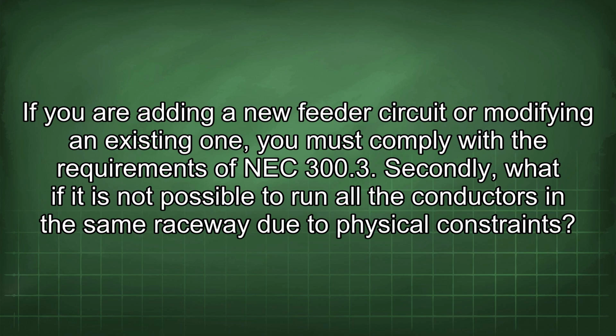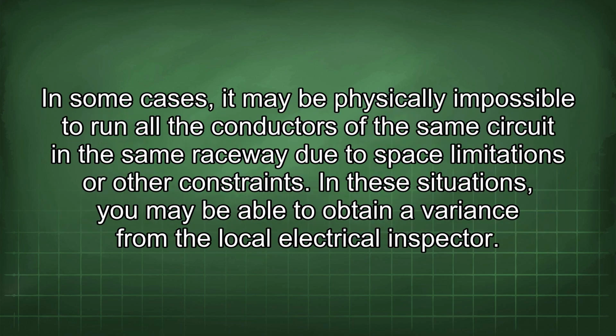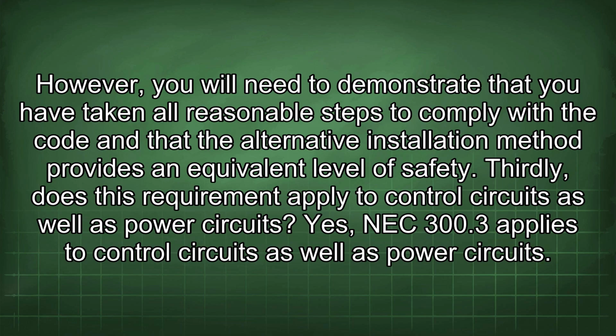Secondly, what if it is not possible to run all the conductors in the same raceway due to physical constraints? In some cases, it may be physically impossible to run all the conductors of the same circuit in the same raceway due to space limitations or other constraints. In these situations, you may be able to obtain a variance from the local electrical inspector. However, you will need to demonstrate that you have taken all reasonable steps to comply with the code and that the alternative installation method provides an equivalent level of safety.